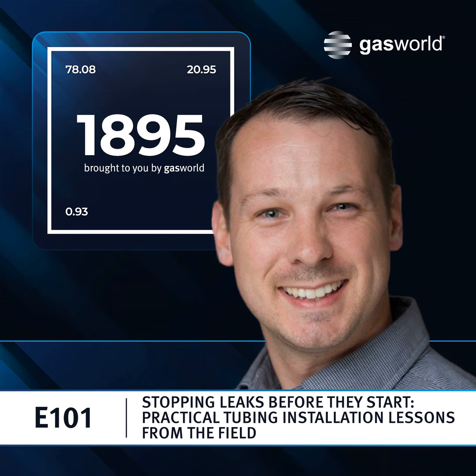The key there, though, is you want to either do it prior to any pressurization or prior to any fluid flowing as you're doing the install, or just be extremely careful that before you break open, the system has been flushed of any hazardous materials or fluids and then fully depressurized. And that's really for when we're talking about MRO type work. We want to make sure that that's taken care of, again, from a safety perspective before we break into any of those fittings.